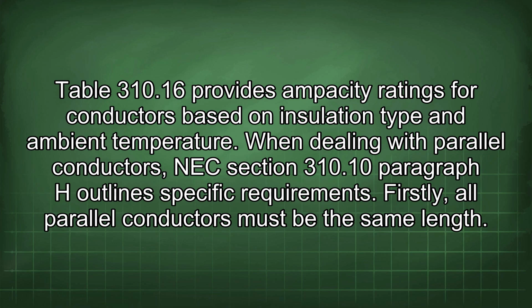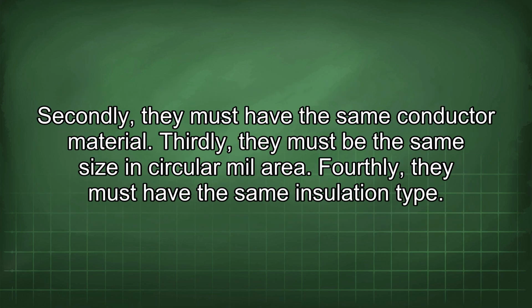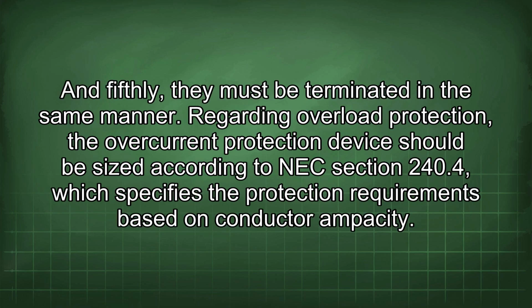When dealing with parallel conductors, NEC Section 310.10 paragraph H outlines specific requirements. Firstly, all parallel conductors must be the same length. Secondly, they must have the same conductor material. Thirdly, they must be the same size in circular mil area. Fourthly, they must have the same insulation type. And fifthly, they must be terminated in the same manner.